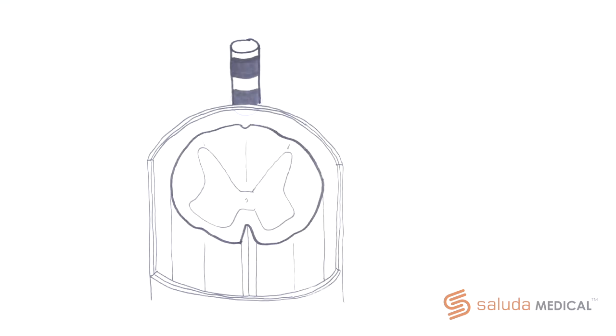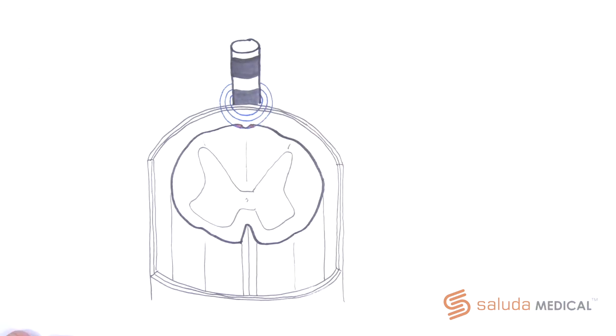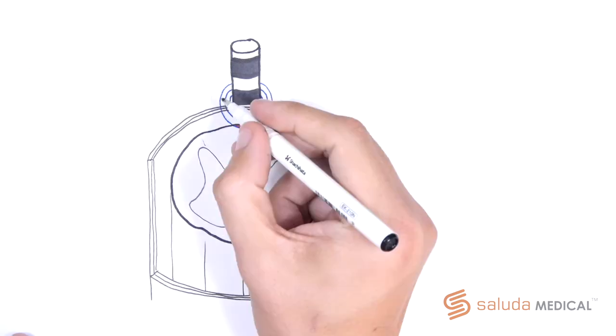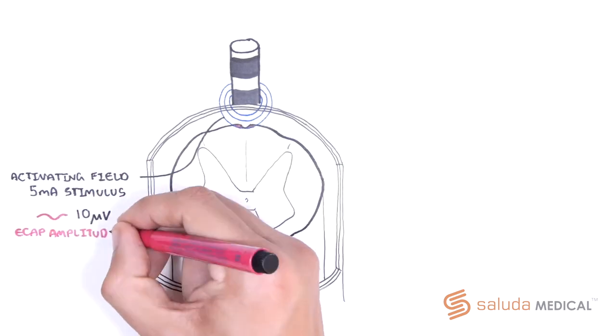If we look at the spinal cord in cross section, with a spinal cord stimulation electrode in the epidural space, we can imagine the activating electric field that is generated by the implanted stimulator around a specific spinal cord stimulation contact. If strong enough, it will penetrate the dura mater, cerebrospinal fluid, and activate a particular volume of fibers in the dorsal columns. These activated fibers will in turn elicit an ECAP the system is able to record from another contact on the same epidural lead. In this example, a 5 mA stimulus has generated a 10 µV ECAP.